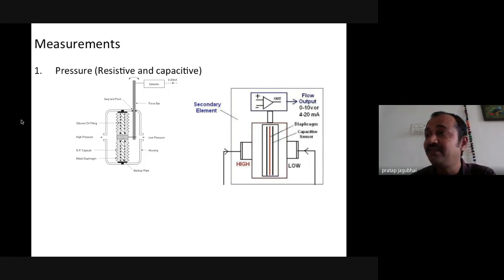So let's start with the pressure. The pressure can be measured with the help of differential pressure as well as static pressure. And to measure the pressure, the very well-known instrument is a strain gauge. So a strain gauge is where the physical property, resistance, varies with deflection, where pressure is equal to force by area, and the resistance is equal to resistivity into L by A, which you know. So resistance is proportional to the length or area in this case.